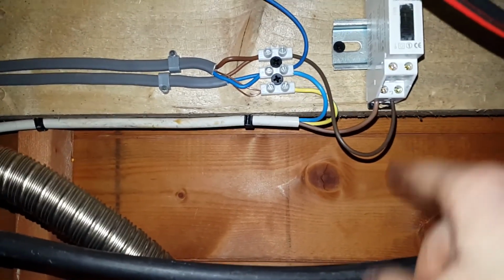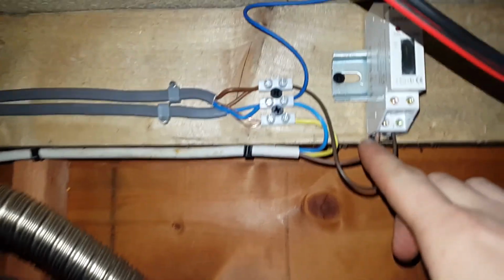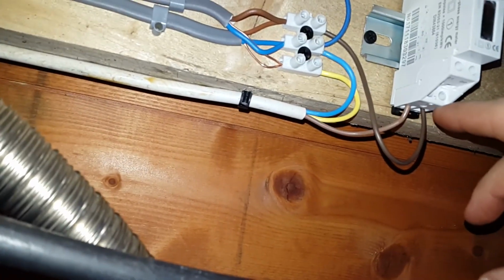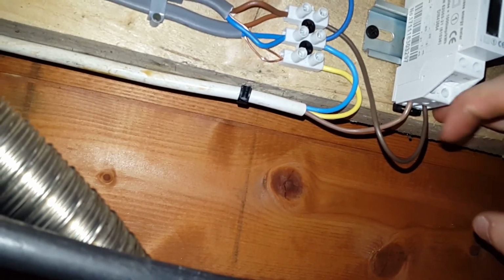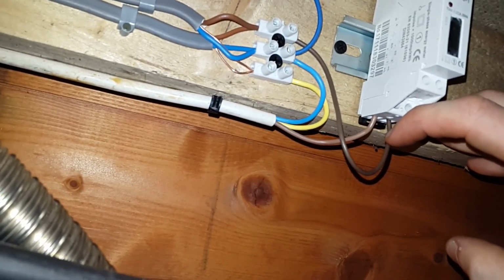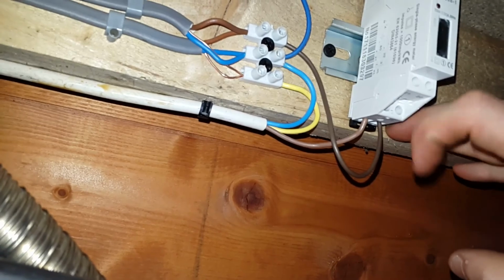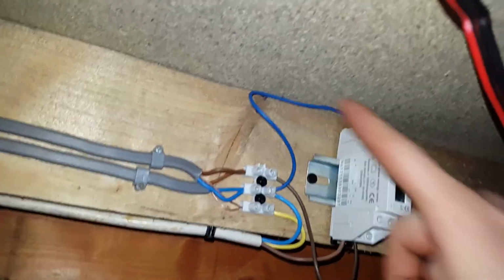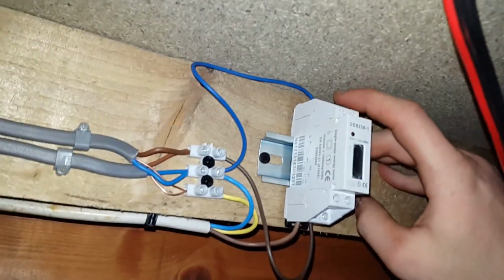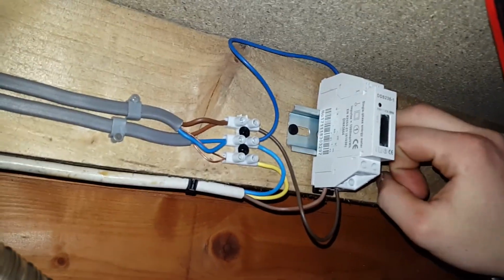Basically the shunt is probably in there somewhere, and your live goes in through connection number 1, and your live comes out again through connection number 3. So in through 1, out through 3, and your neutral just goes into number 4, and that's just to power the unit.